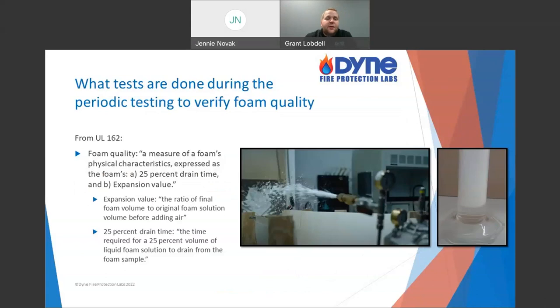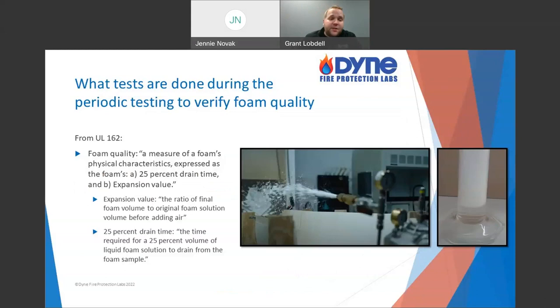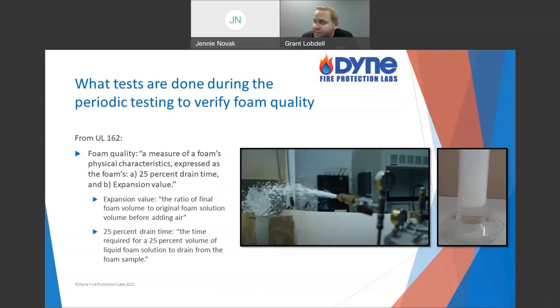You'll notice that it said foam quality condition testing. What do we define as foam quality? In NFPA, there is no formal definition. In chapter 3 of every NFPA standard is a section on definitions — there's no foam quality specifically defined, unfortunately. But it is inferred in a lot of the annex. They talk about foam quality, and they have annexes on tests discussing expansion and drain time.